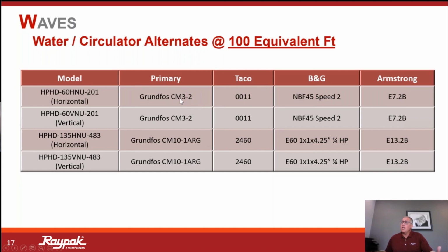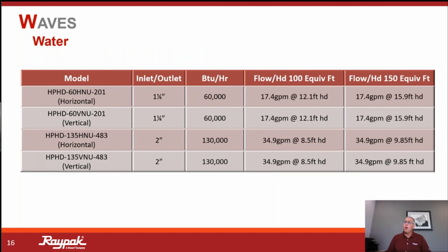And this particular bandwidth of selections is 100 equivalent feet. So we can talk about pressure drop, but more or less, if we look at 100 equivalent feet, these would be the circulators from your, let's just say, primary brands: Taco, B&G, Armstrong. Now, again, I am not limiting the other manufacturers that might be out there. You might have Wilo, you might have Gould pumps. There's different pump availability out there. So this is a good baseline to cross reference to. And again, I do list the flow and head requirements on slide number 16. Okay, so here we are looking at 100 equivalent feet. And then we also have some flow and head requirements if you're 150 equivalent feet away.